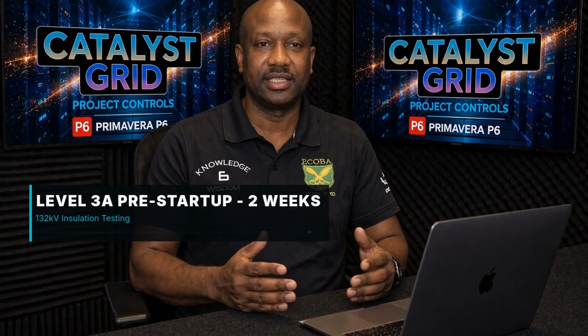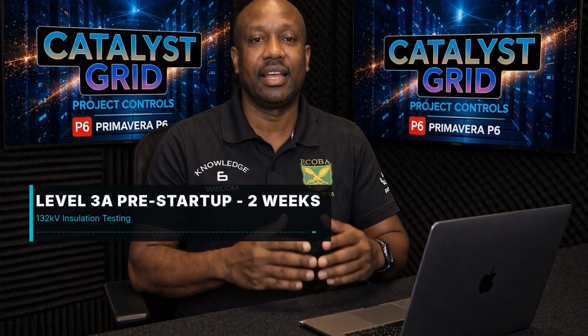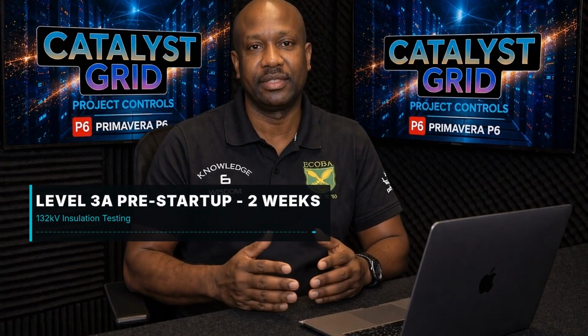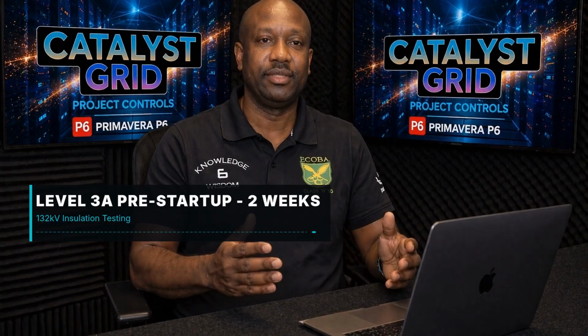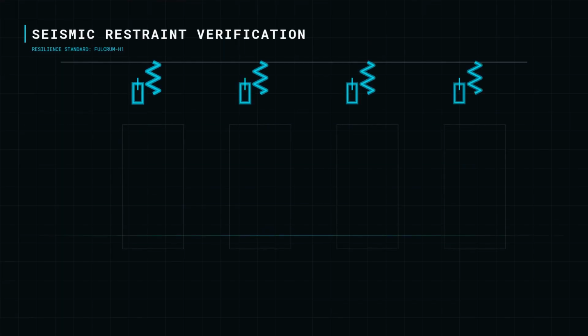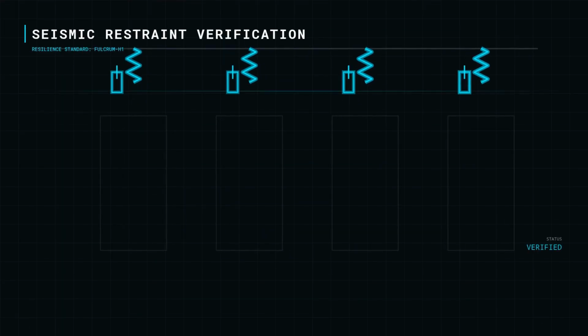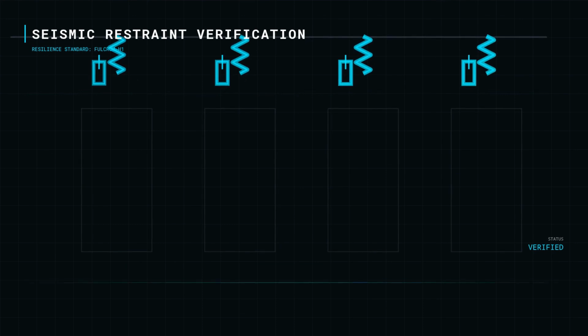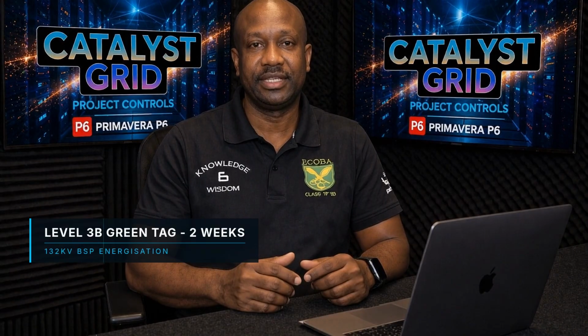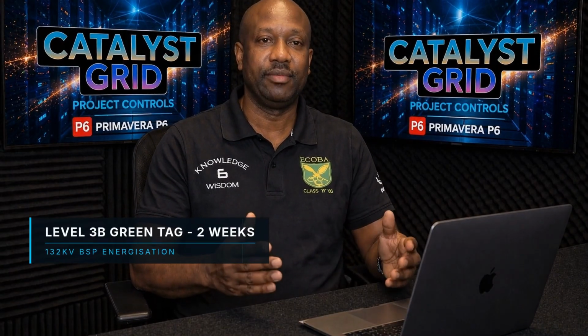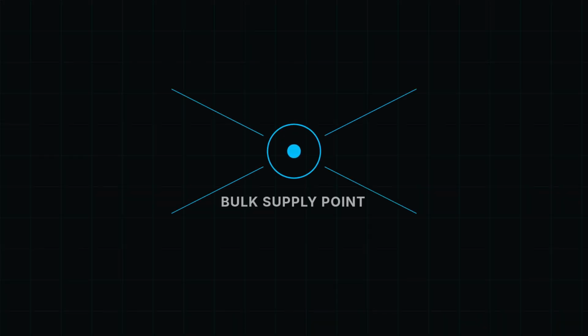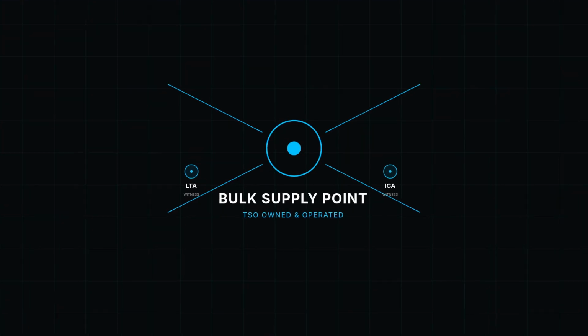Level 3A pre-startup covers insulation resistance testing at 132 kilovolt levels, a significant leap from the 11 kilovolt distribution at Iron Gate. We also added seismic restraint verification for all MEP services, a new requirement for FULCRUM to meet stringent hyperscale resilience standards. Level 3B green tag is the single most significant commissioning event, the 132 kilovolt bulk supply point energization. The BSP is owned and operated by the transmission system operator. Our team attends as witnesses, but the TSO switching team is in control.